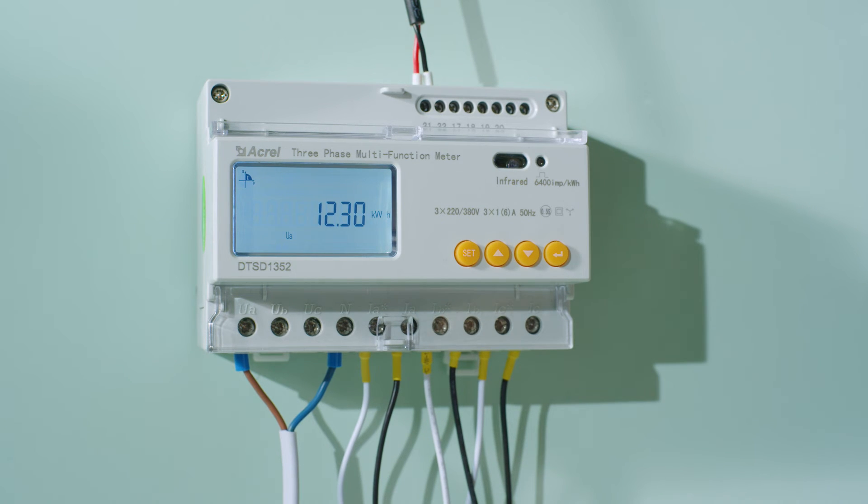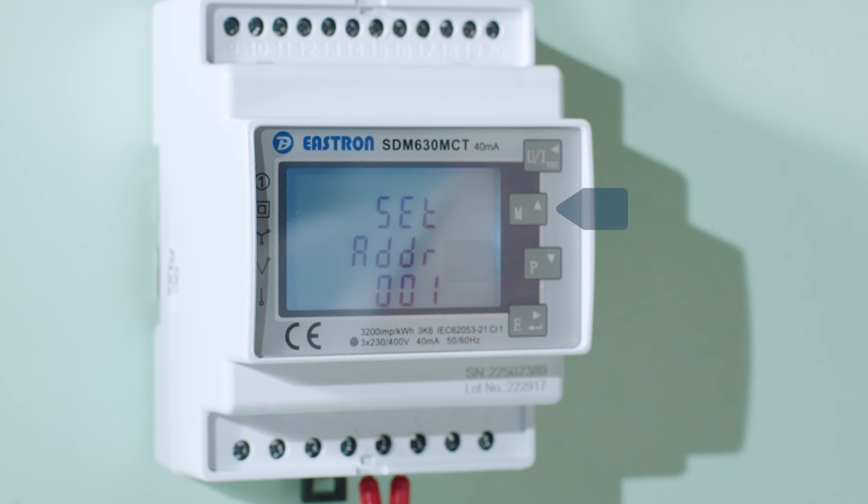For Eastron models, hold the button until the display shows the PASS interface. Use the arrow buttons to enter the code 100. Hold the button until the setting menu appears. Use the arrow up and arrow down buttons to scroll through the different options in the setup menu. Please note that the up and down arrows give different results. The CT setting is for setting the CT ratio of the current transformer that is connected to the meter. For this model, the secondary CT value (CT2) is fixed to 40 milliamps.